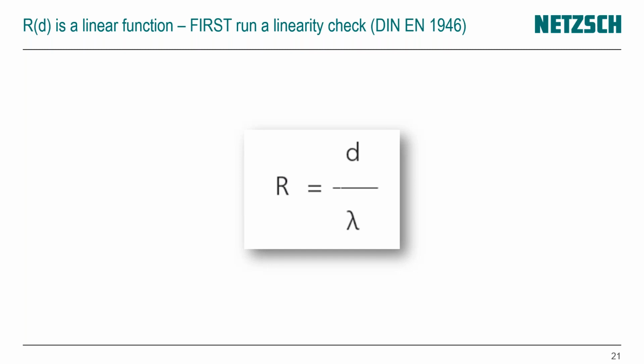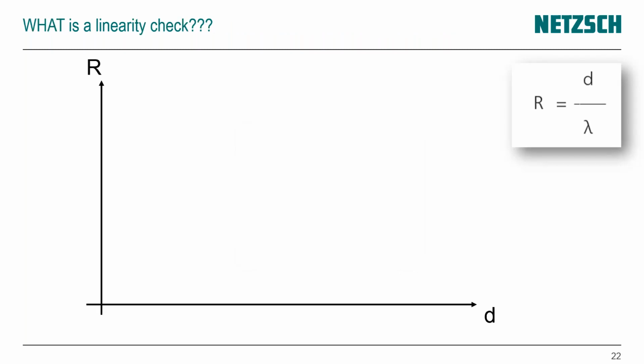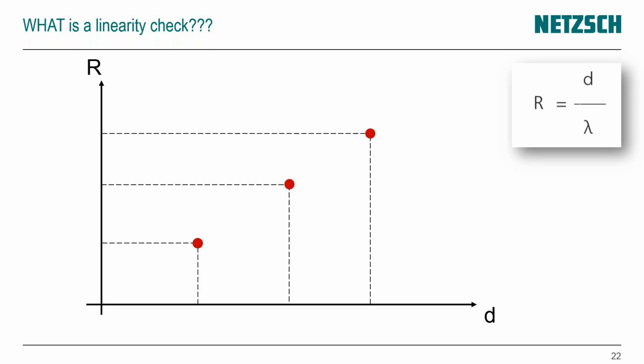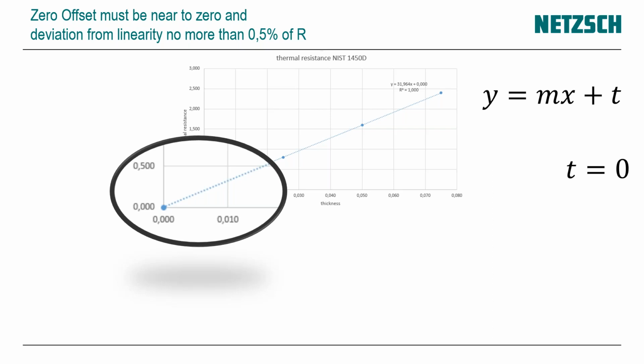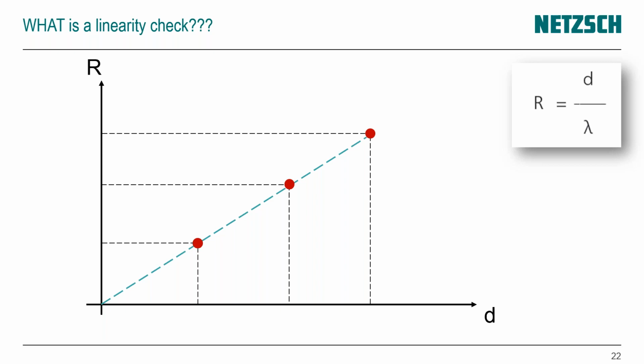What you see here is the equation for the thermal resistance of a material, which is thickness divided by thermal conductivity. Our instrument gives as a result the thermal conductivity and the thermal resistance. And if you plot the thermal resistance over the thickness, keeping in mind that R is thickness divided by lambda, which is a linear function, you should get a linear curve in that case. Of course, if the thickness of your sample is 0, the thermal resistance is 0. This is the reason why this linearity check should go through the origin.